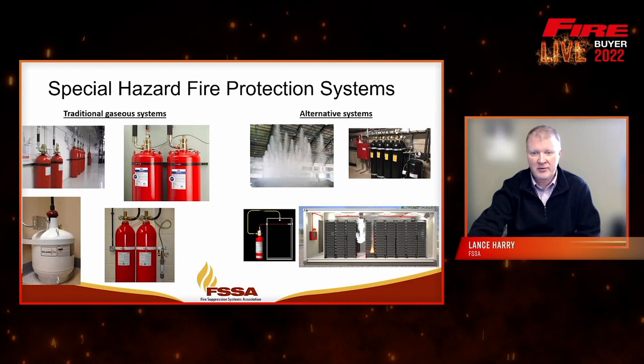That system is used in a variety of applications. Here it's actually an aircraft hangar, a nice alternative to a traditional sprinkler system in that type of application. In most cases, you can use anywhere between 75 to 90% less water than a traditional sprinkler system with a water mist system.